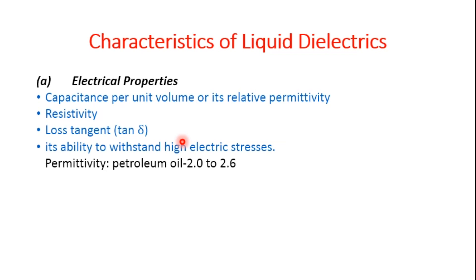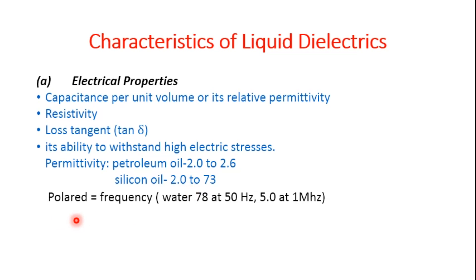The power factor is an indication of power loss under AC applications, along with the ability to withstand high dielectric stress. The permittivity for most petroleum oils varies from 2 to 2.6, while that of silicone oils varies from 2 to 7.3. In the case of non-polar liquids, permittivity is independent of frequency, whereas in polar liquids such as water it changes with frequency. For example, the permittivity of water is 78 at 50 Hz and reduces to about 5 at 1 MHz.